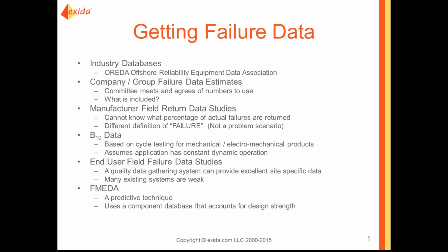There's a technique used for calculating mean time to fail or useful life of a product, which is sometimes referred to as a B10 analysis. There's end-user specific studies where end users look at their populations of equipment and their experienced failures. And then finally, there's the modeling technique, FMEDA, which uses a database of component failures to model and predict the reliability for an assembly. So we're going to take a look a little bit at each of these different sources.